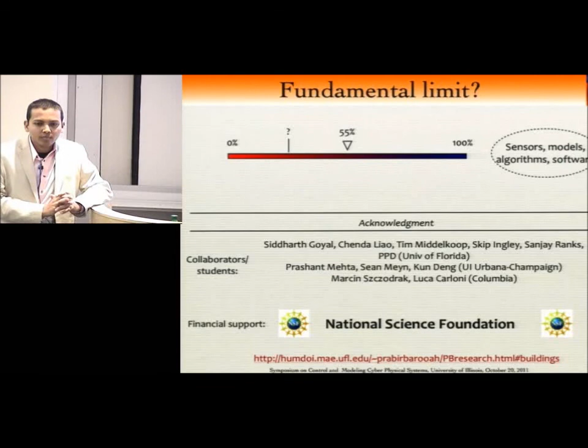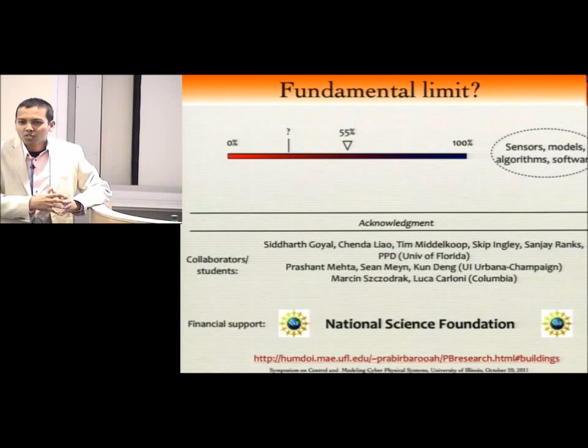Well, in terms of the fans that circulate air, that's what I read too, that they consume a lot of energy. But I'm not quite sure, because we looked at energy consumption from the fans in this building using the VFDs, variable frequency drives. Over a period of a month, we saw that fans were actually consuming only about 10% of total energy consumption, much lower than the numbers I'd been reading. I don't yet know why that is. Maybe reheating, as shown in the plots, consumes about 30 or 40% of the energy, so maybe reheating is so much higher that it's pressing down the fan energy share. But all of these components are important, first the cooling and the fans, and then the reheating at the end.